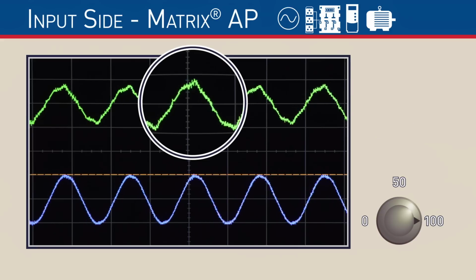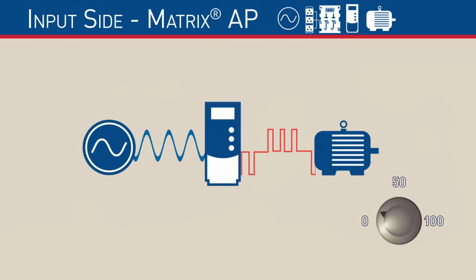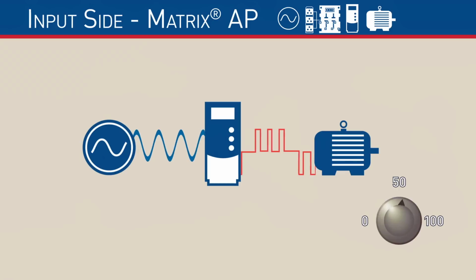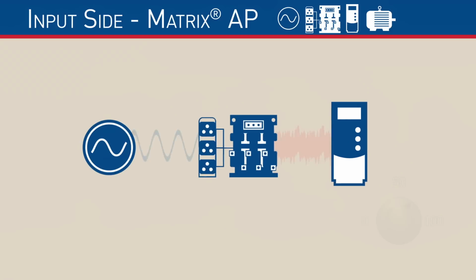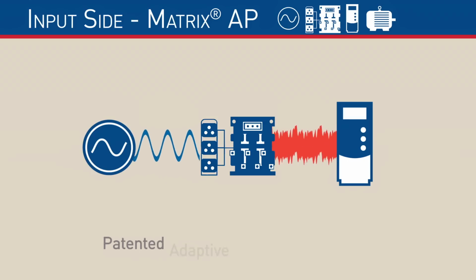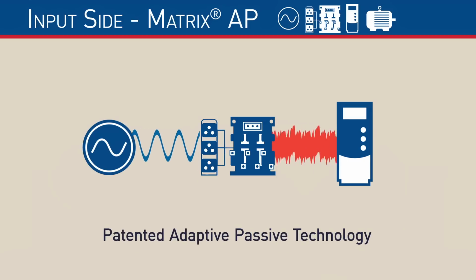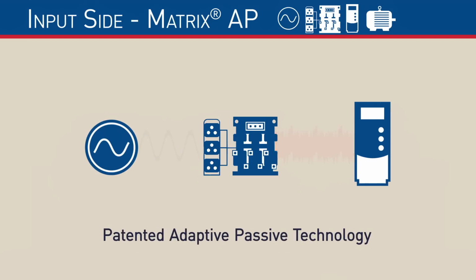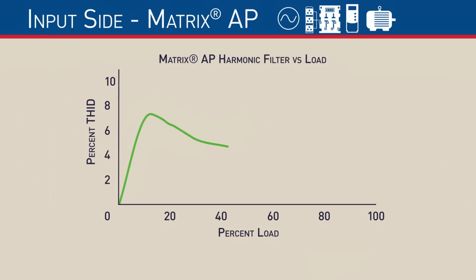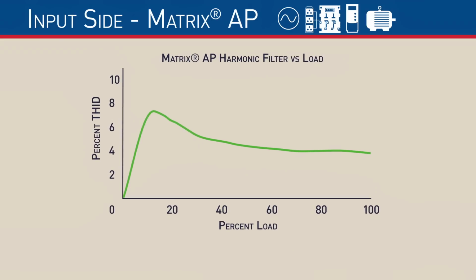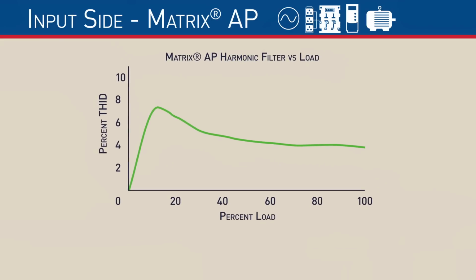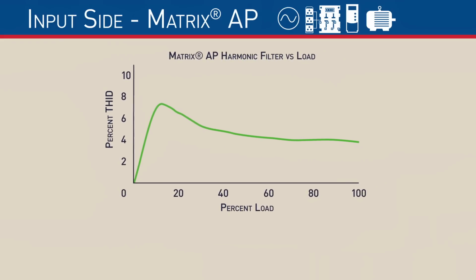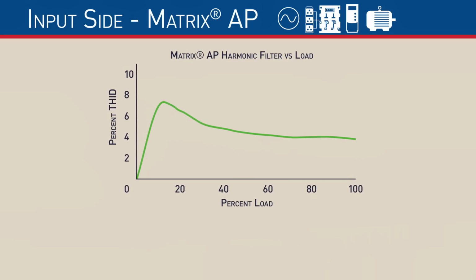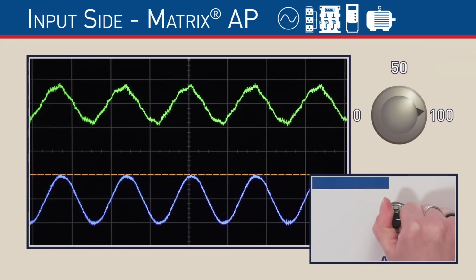However, this is at 100% load. Since VFDs allow varying motor speeds, systems using them rarely run at full load. Unlike other filters, the Matrix AP's patented adaptive passive technology utilizes a revolutionary reactor core that allows it to adapt its impedance in response to changing loads. The result is consistent, low harmonic performance over a wide load range. The technology also delivers a filter with low capacitance, meaning it has a low leading power factor and can be used in generator applications. Let's see the AP technology in action.